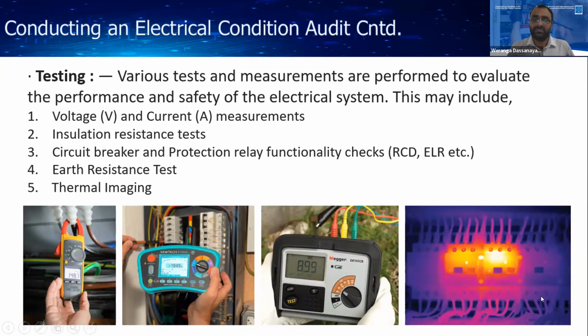I think the fourth image shows you using a thermal imaging camera, which is used to see the condition of a system, and this is mainly used in energy audits also, because condition audits and energy audits are almost the same, but mostly energy audits are concerned about the power saving of the system, and condition audits focus on the healthiness and the safety of the power system, while energy audits are concerned with energy saving of the system. So the thermal imaging part we use in both condition audit and energy audit.